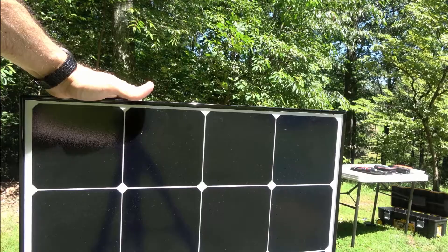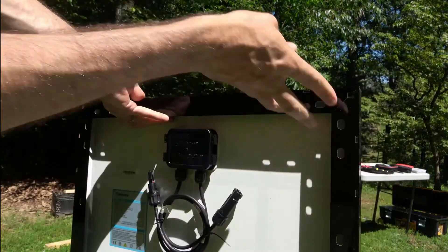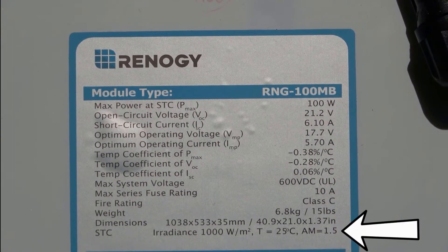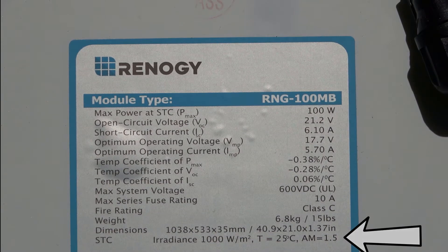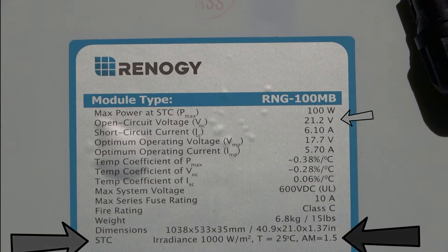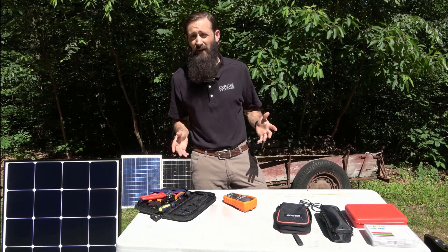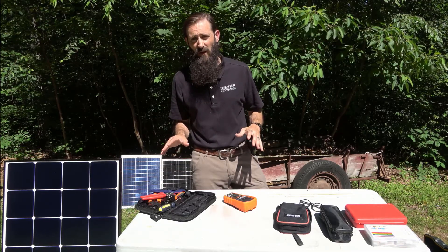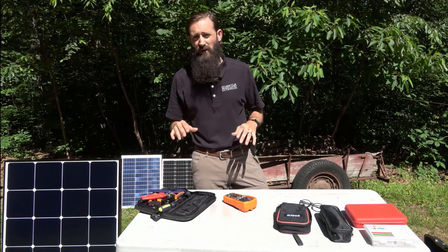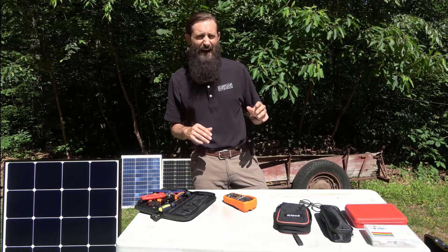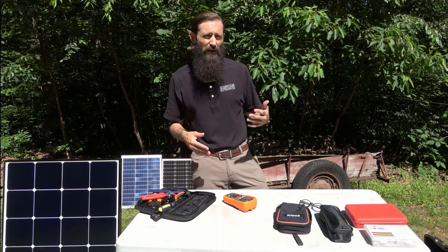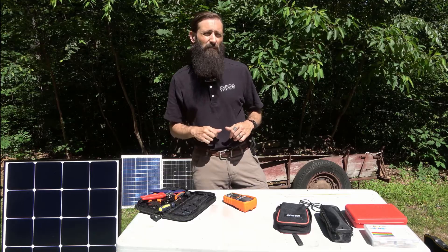Before we start, we'll take a look at the ratings for this solar module under Standard Test Conditions, or STC, by looking at the specification label on the back of the module. The STC conditions are 77 degrees Fahrenheit (25 degrees Celsius), 1,000 watts per square meter of irradiance, and an air mass of 1.5. Under STC, the module should read an open circuit voltage of 21.2 volts and a short circuit current of 6.1 amps. A significant reduction of 40–50% in voltage could indicate a problem such as a blown diode within the junction box.